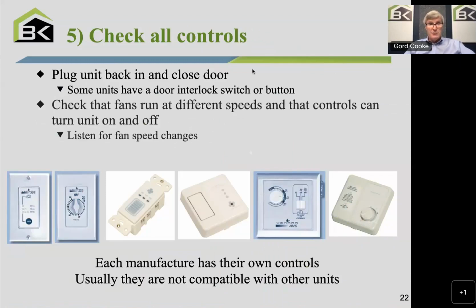That's for safety reasons. But what you want to do is check that the fans run at different speeds. So you're going to do the control at low speed, high speed, make sure you hear the fans moving at different speeds. Listen for those fan speed changes. And each manufacturer has their own controls down there at the bottom. Usually they're not compatible with other units. I know that's kind of weird, right? Thermostat you can use on anybody's furnace. The HRV manufacturers still each have their own controls, and they're not compatible.